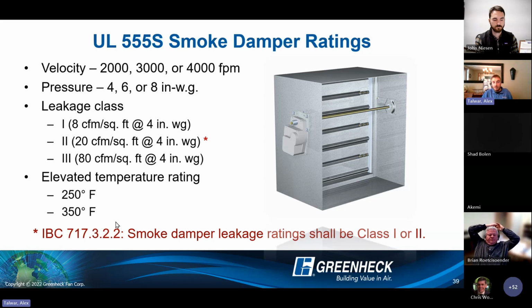And although it is a smoke damper and we are not testing it against fire, we are still testing it under elevated temperature because it will potentially need to operate at an elevated temperature in a fire event. Again, the purpose of the product is not to prevent the spread of flame, but it does need to operate in these types of conditions.